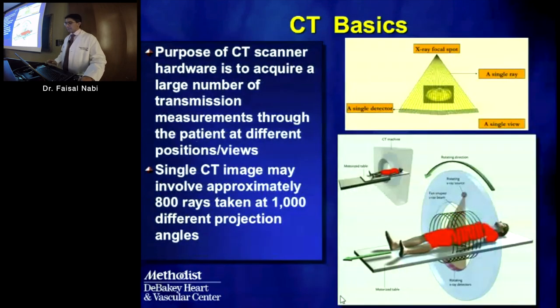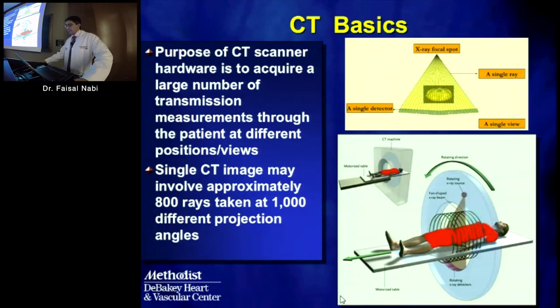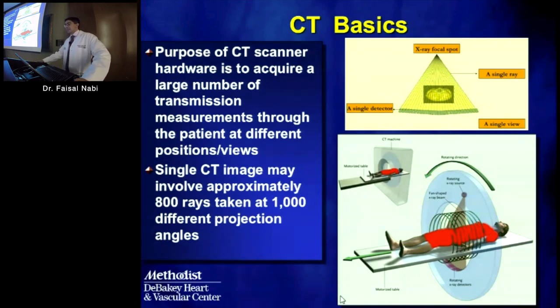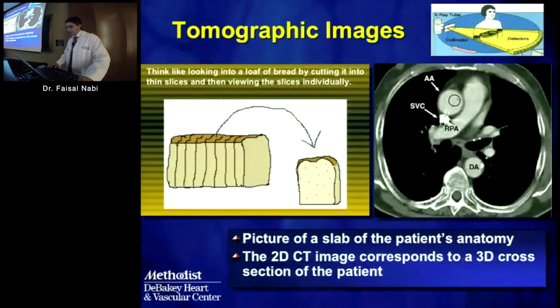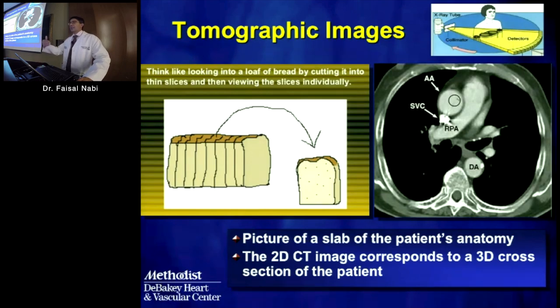A CT machine consists of a motorized table, an x-ray source, the patient in the middle within the bore, and x-ray detectors on the opposite end of the x-ray source. Rays of radiation are transmitted through the patient in a cone-shaped fashion in current-day scanners. You can think of CT as creating axial 2D images like slices of a loaf of bread—each image represents a particular slice location or slab of the patient's 3D anatomy.